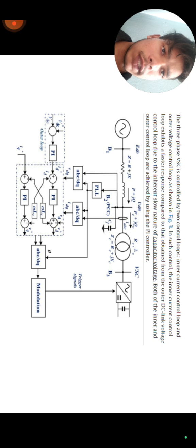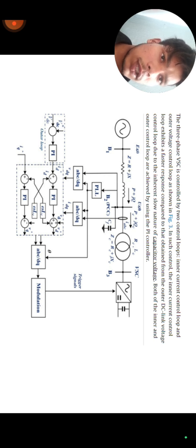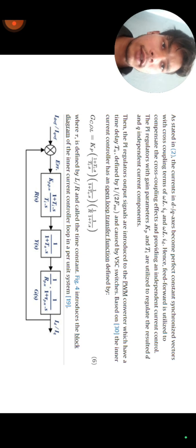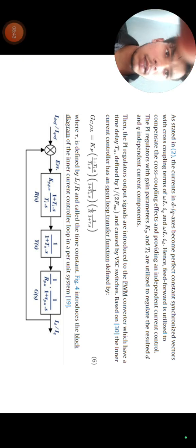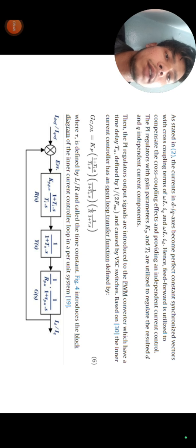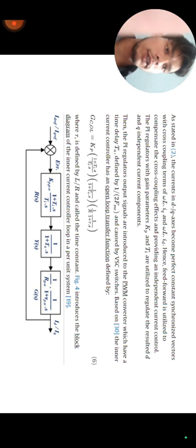The diagram shows R plus jX, P plus jQ, Pc plus jQc, PLL, abc to dq, PI, PWM, and modulation. So the currents in the dq axes become a perfect constant synchronous vector with cross coupling terms of ωL Iq and ωL Id. Hence, feed forward is utilized to compensate the cross coupling effects and provide independent current control. The PI regulators with gain parameters Kp and Ti are utilized to regulate the resulting D and Q independent current components.